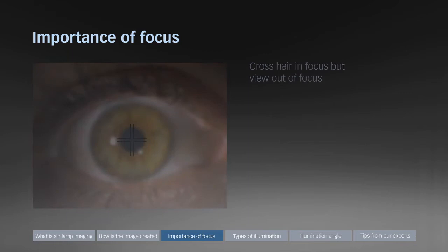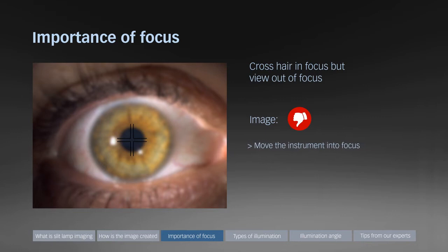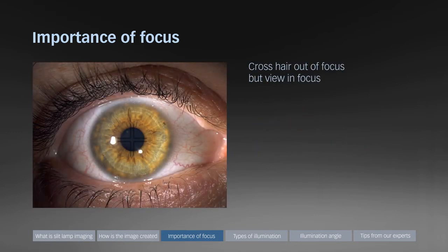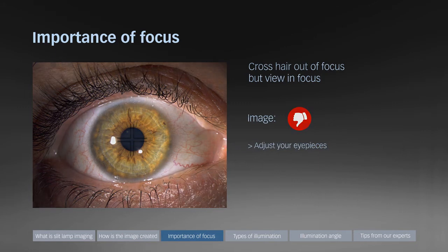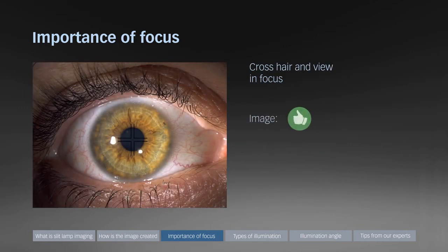If by looking through the eyepieces the crosshair is in focus but the view is out of focus, you need to move the slit lamp into focus. If the crosshair is out of focus but the view is in focus, you need to adjust your eyepieces. If the crosshair and the view are both in focus, you can be sure that the captured image is going to be perfectly in focus.